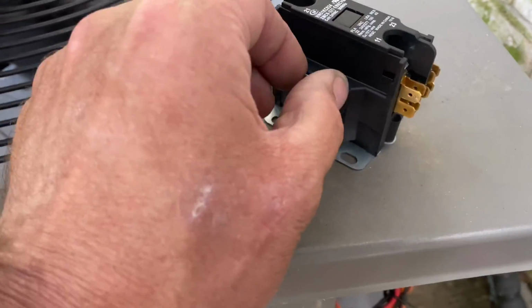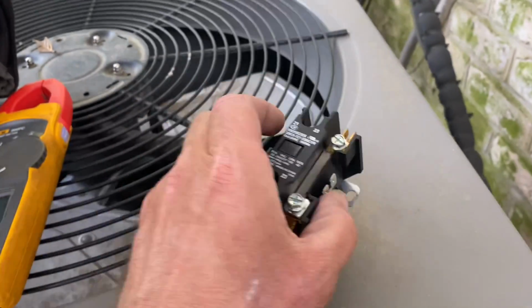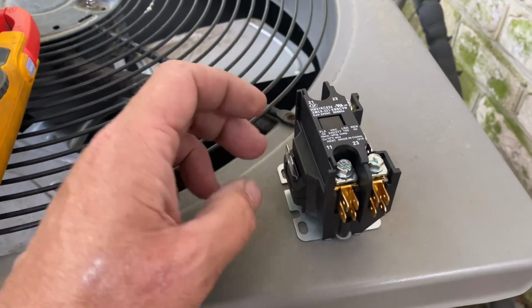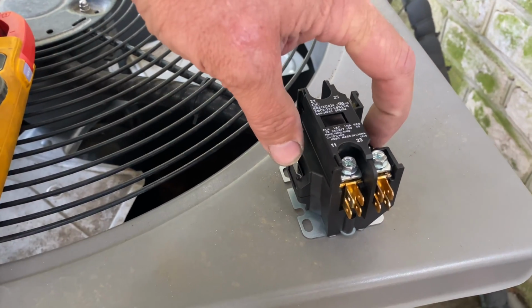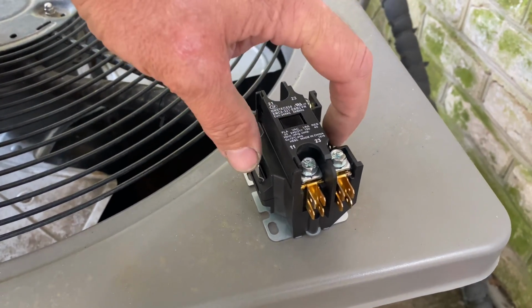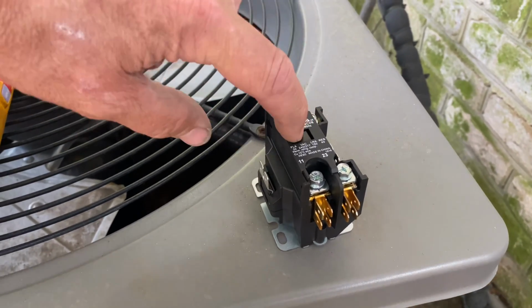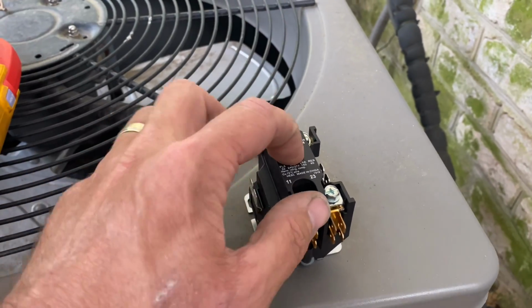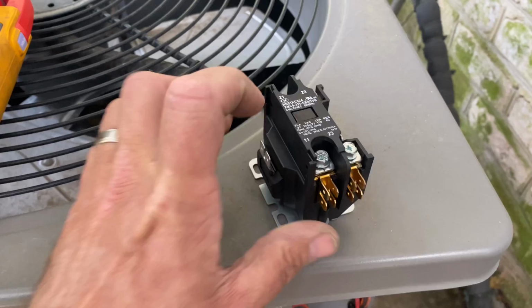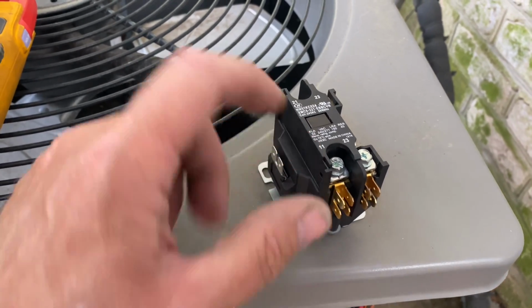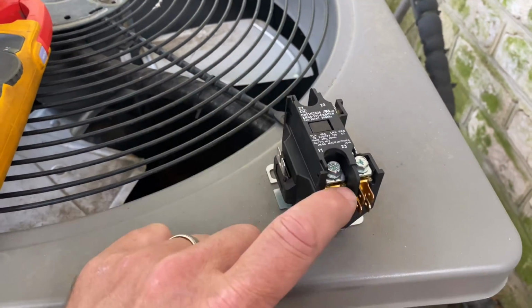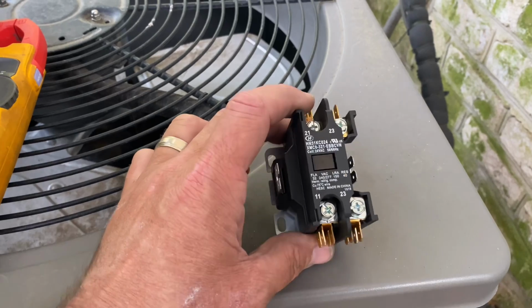Here, on this side and this side, we have a coil inside here. There's a 24 volt coil. So when 24 volts is applied to these two sides, where my thumb and my pointer finger are, it closes the contactor and pushes that pole in, and then T1 will be energized from L1. Power will flow across here, right?